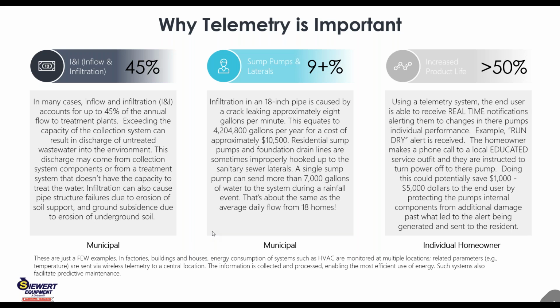A run dry on this specific pump, if it required a full motor rebuild, could have meant a new pump replacement plus install costs pushing $5,000. If we caught it fast enough and still had to come out and do lower end work, that still would have saved at least $1,000 on this call. And to an individual homeowner, that's big money.